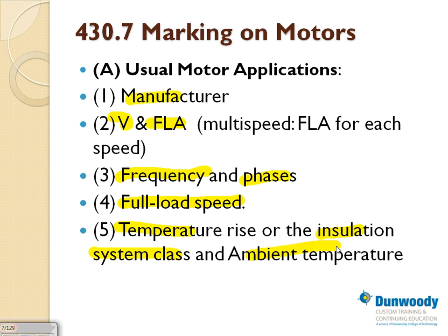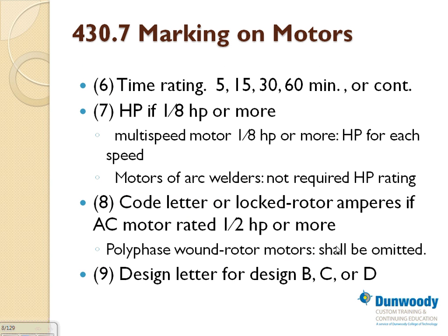So if you look at the nameplate of a motor, by code, all this information has to be listed for every motor. A couple of other things that they can give you too: time rating. For example, you have an air handling unit. The blower on the air handling unit is continuous duty. That can run continuously. There are motors that can run for cycles of 30 minutes, or 5, 15, 30, or 60 minutes, if it cycles on and off. Most of the motors that we use in the construction industry are for the most part continuous duty. Unless you have a specific function, most of them are continuous duty.